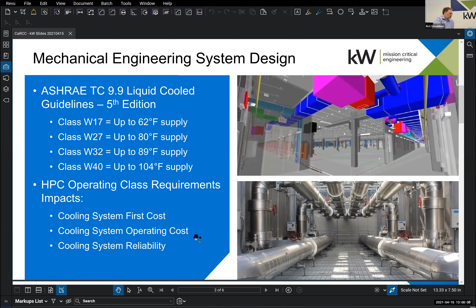So here's what a system might look like for a W17 or W27. A lot of parts and pieces here. You'll see here's your high performance compute load. But to keep that cool, typically we might need a cooling tower sitting outside rejecting the heat. We would have probably some sort of a heat exchanger that allows us to decouple the precision water we need at the load from this open cooling tower loop.